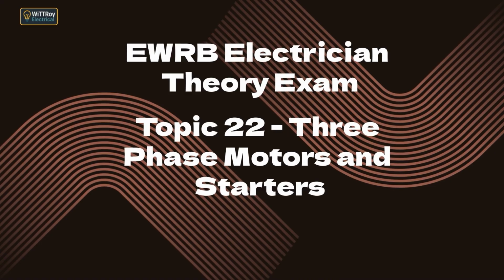Topic 22.3e. Describe the operation of the following types of reduced voltage starters, including advantages, disadvantages and applications. 1. Star-delta starter. Operation: the motor starts in star. Each winding receives only line voltage divided by root 3. Starting current and torque are reduced. After acceleration, the timer switches the windings to delta, allowing full voltage and full torque.